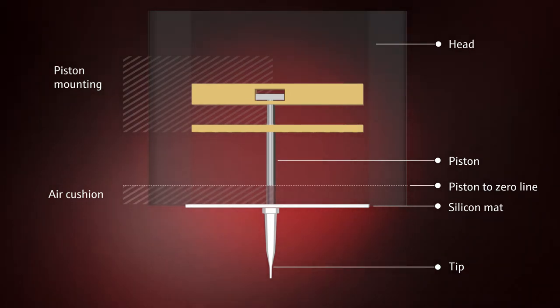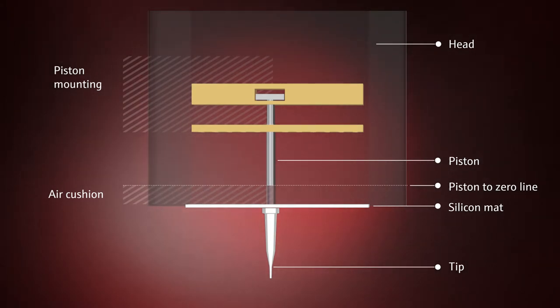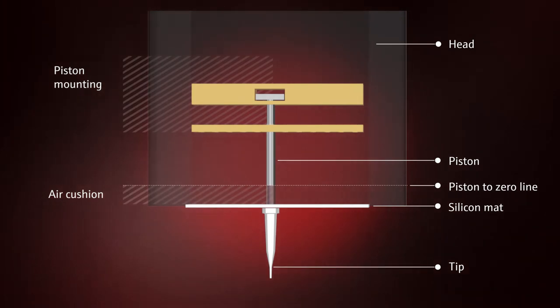A cushion of air is always located between the piston and the liquid sample in the tip. The silicone mat ensures an airtight seal between the tips and the head.